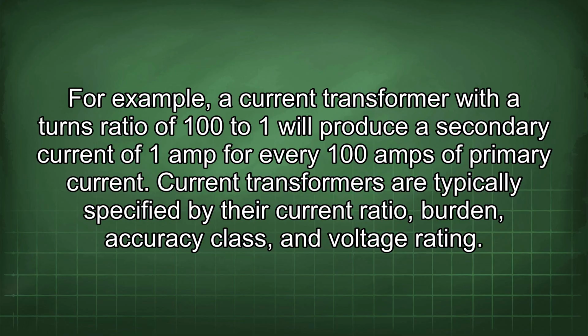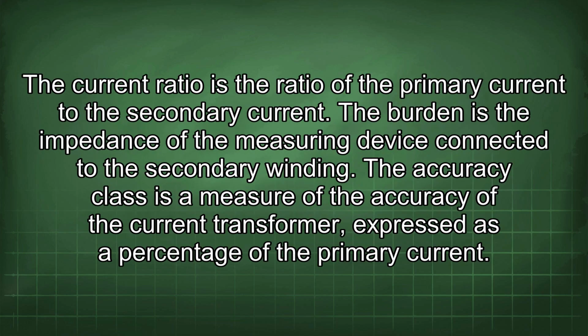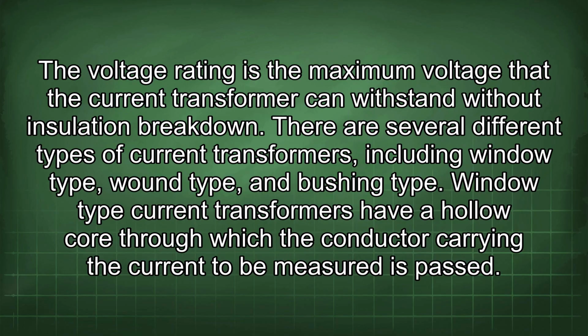Current transformers are typically specified by their current ratio, burden, accuracy class, and voltage rating. The current ratio is the ratio of the primary current to the secondary current. The burden is the impedance of the measuring device connected to the secondary winding. The accuracy class is a measure of the accuracy of the current transformer expressed as a percentage of the primary current. The voltage rating is the maximum voltage that the current transformer can withstand without insulation breakdown.